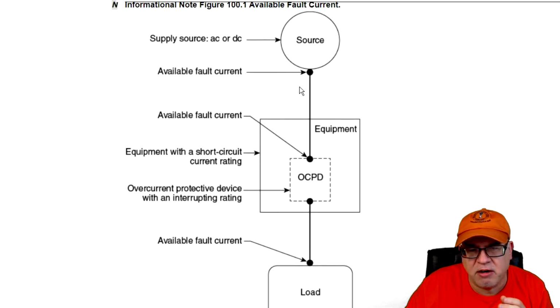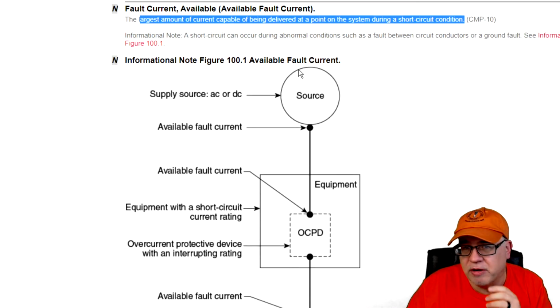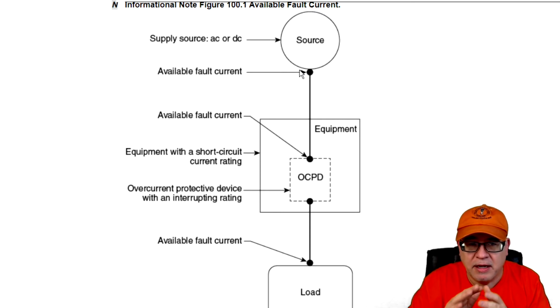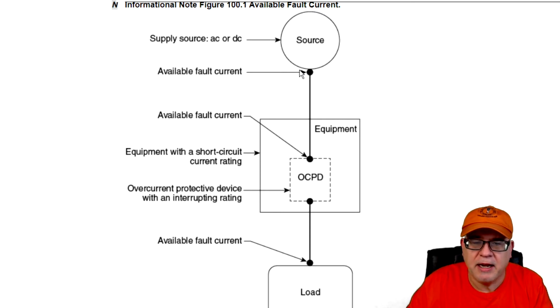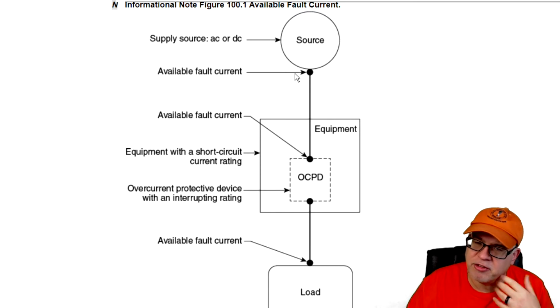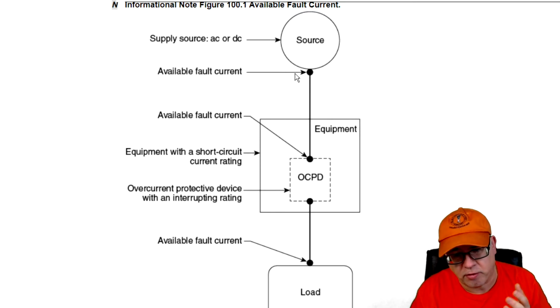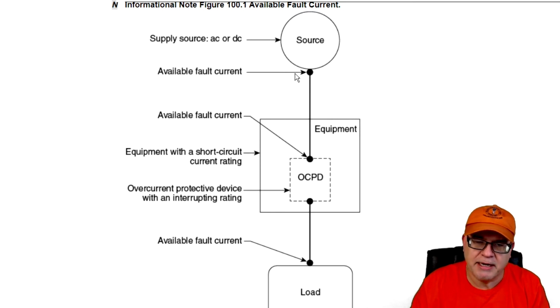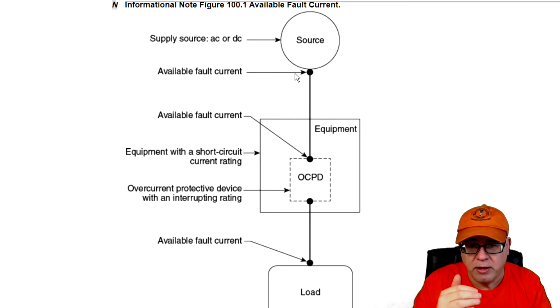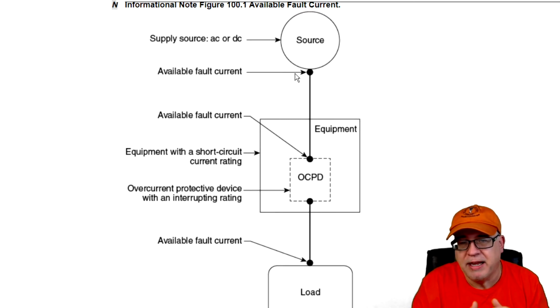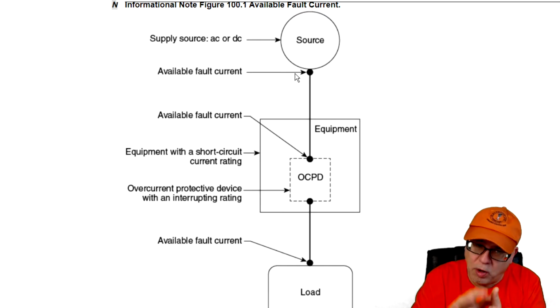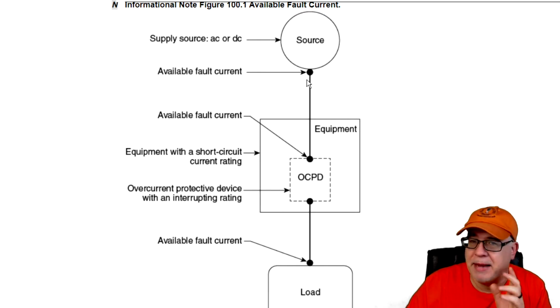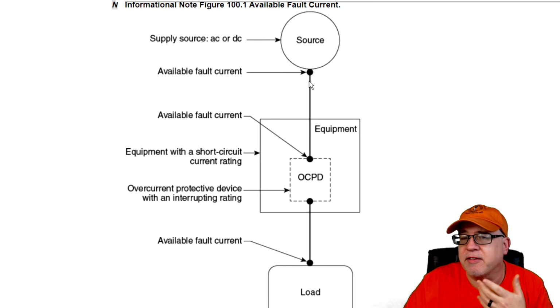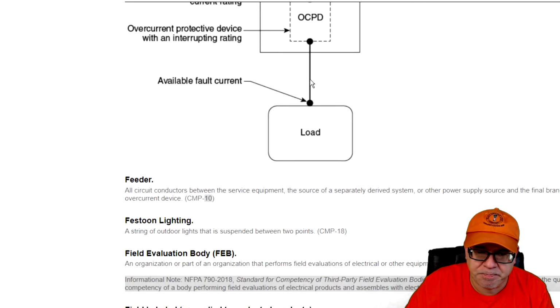So you see here that the National Electrical Code has now instituted this infographic, this figure, and it really does help simplify understanding the difference between short circuit current rating, that's the equipment, interrupting rating, that is the device, and available fault current, which is at any point on the node where I need to connect to another piece of equipment or connecting from a piece of equipment. I can calculate out what that available fault current is, its maximum value. And then we can design the equipment around that, right?